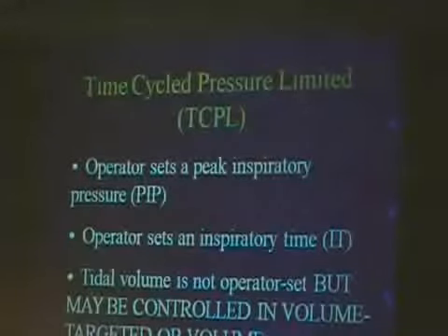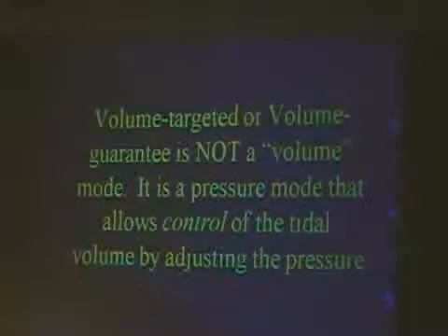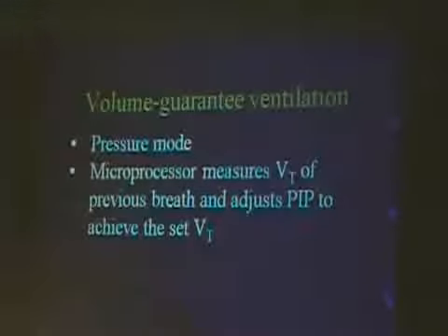But the ventilator can control the volume using a microprocessor. So volume targeted or volume guaranteed, which we are going to be doing, is not a volume mode. It is a pressure mode that allows control of the tidal volume by adjusting the pressure. Really, really important, all right? It will control your tidal volume by adjusting the pressure. So it's a pressure mode.